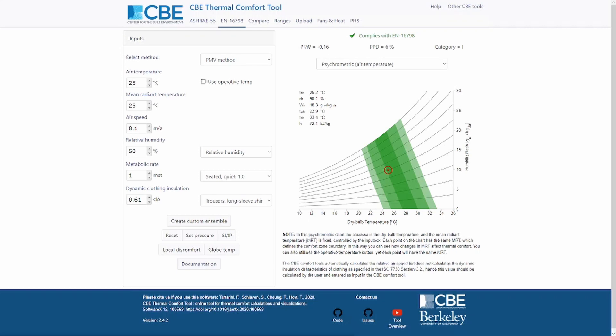They are the main tabs because they allow you to calculate the PMV model in accordance with the two main international standards. One is the ASHRAE 55, which is currently in its 2020 version, and the other is the EN16798, which is a European standard. The calculation of the PMV in the EN16798 standard is based on the model presented in ISO 7730.